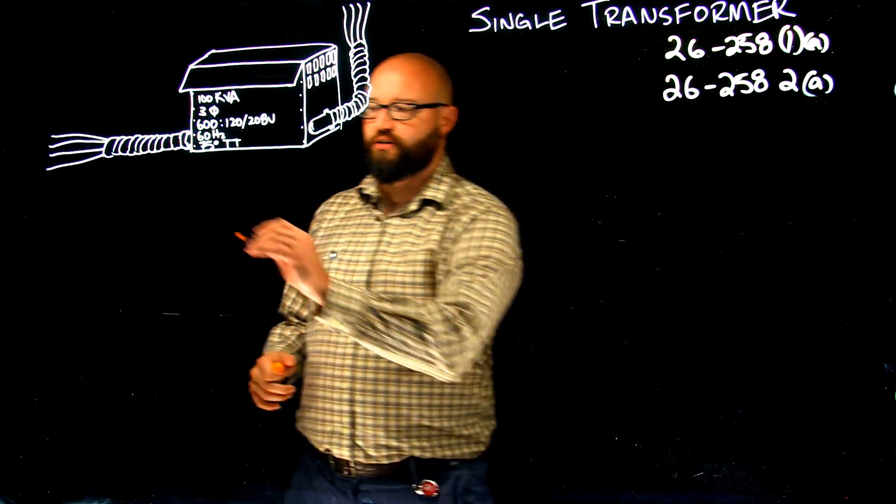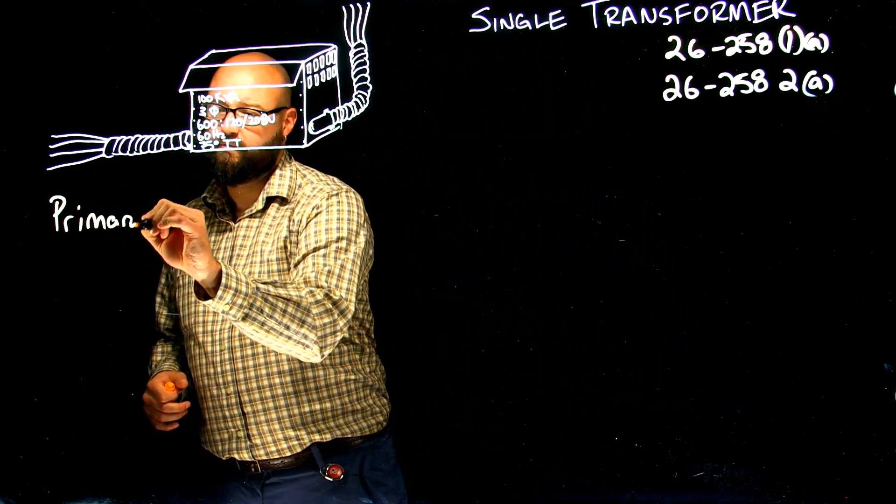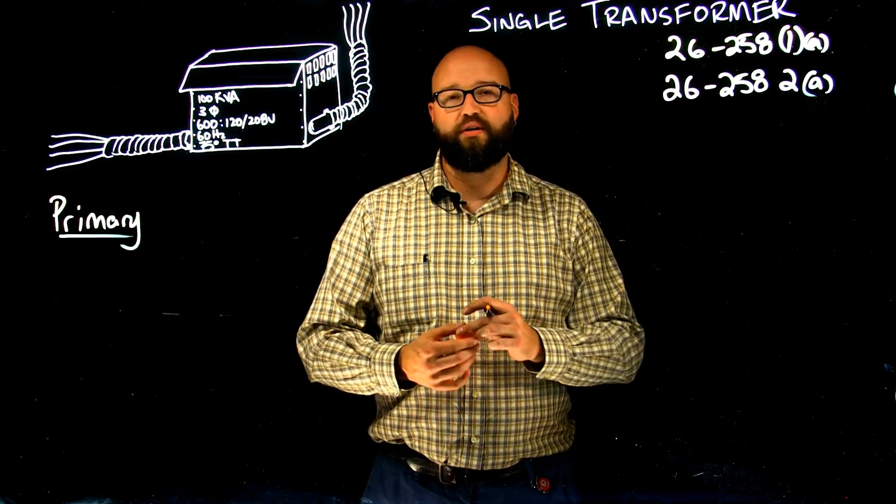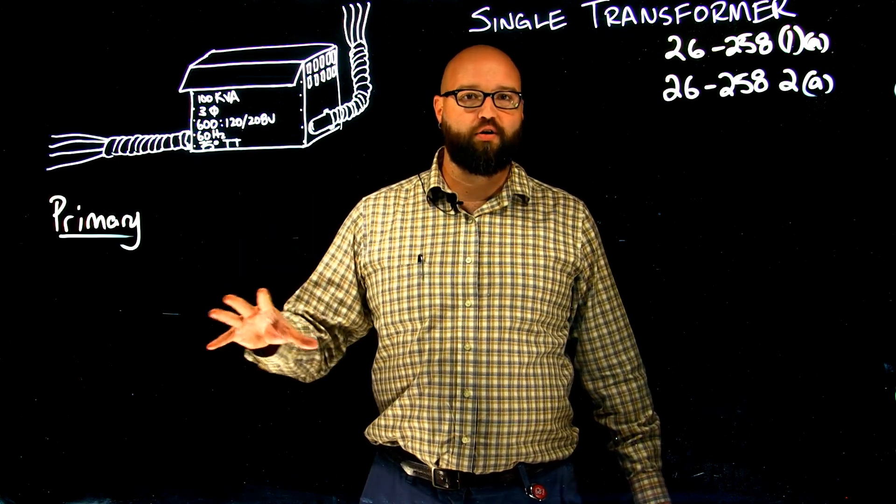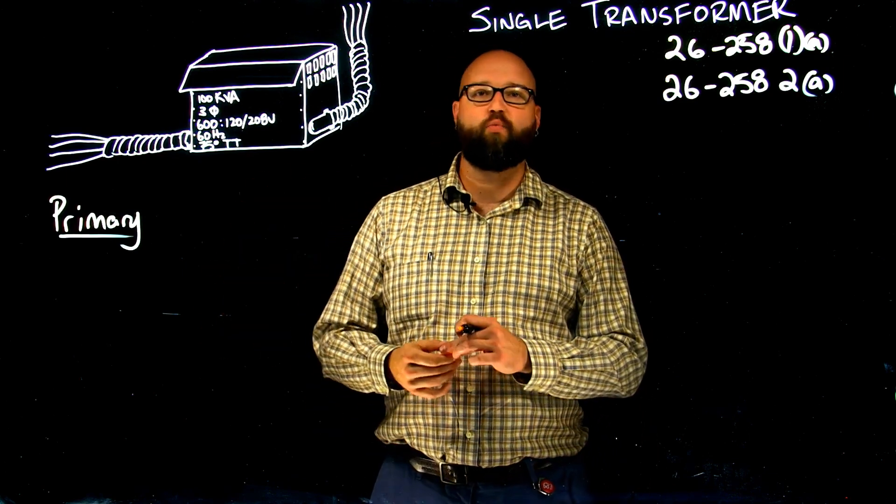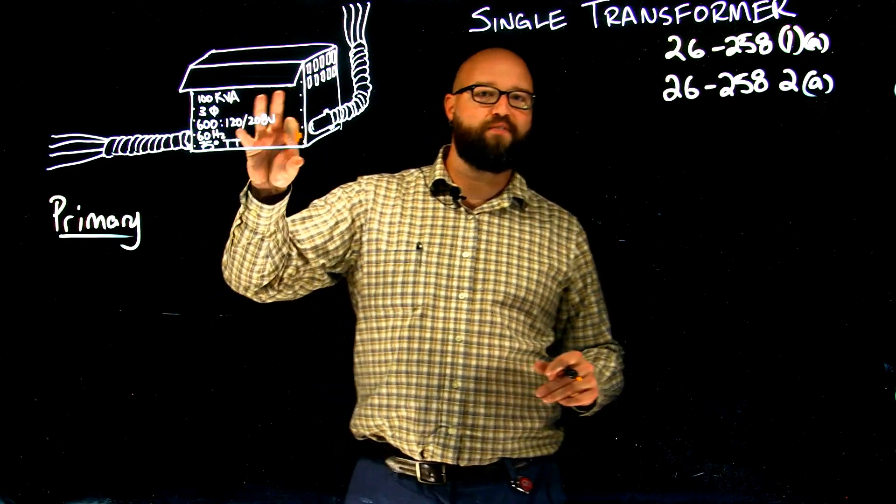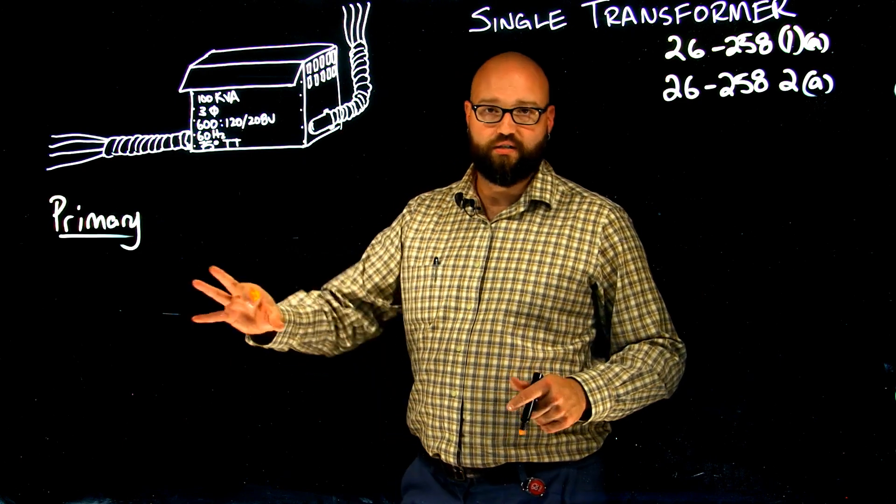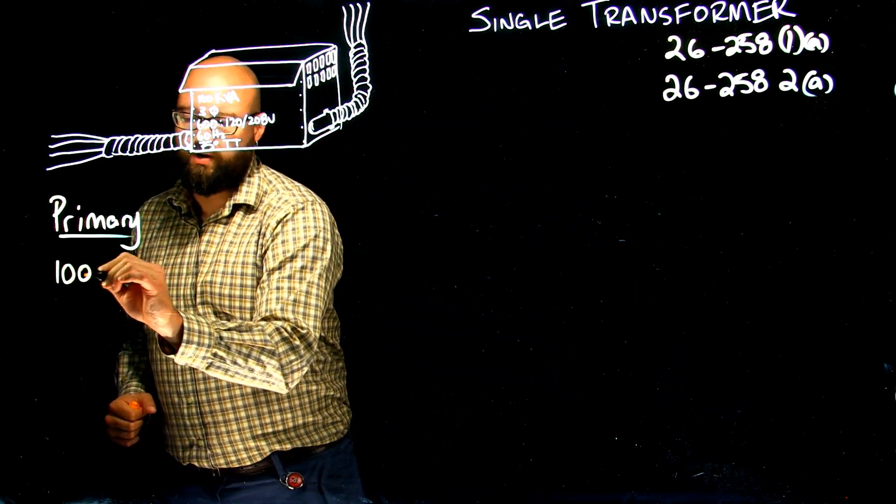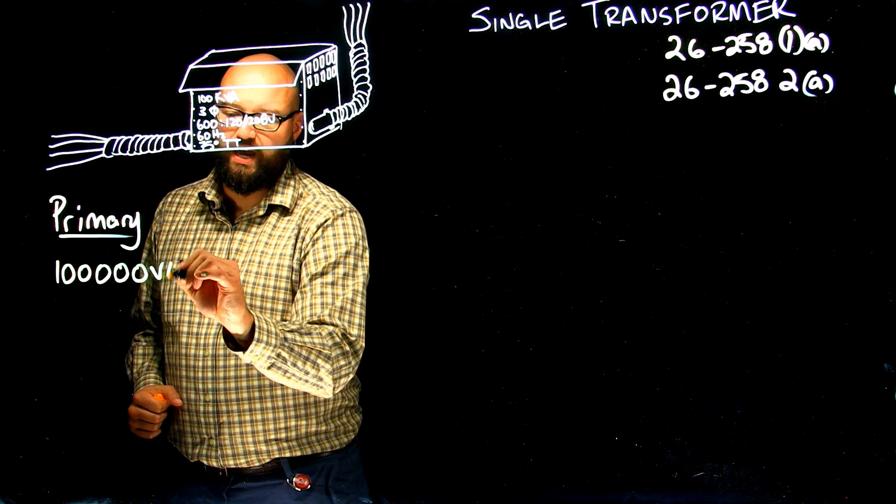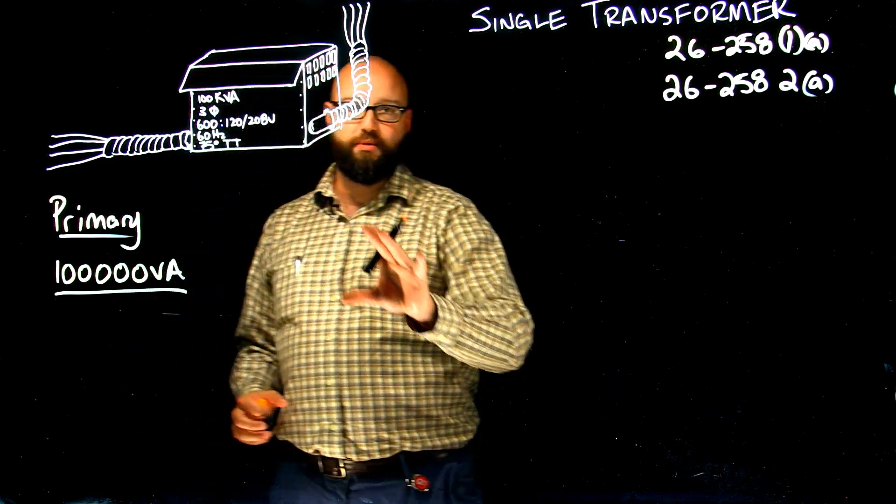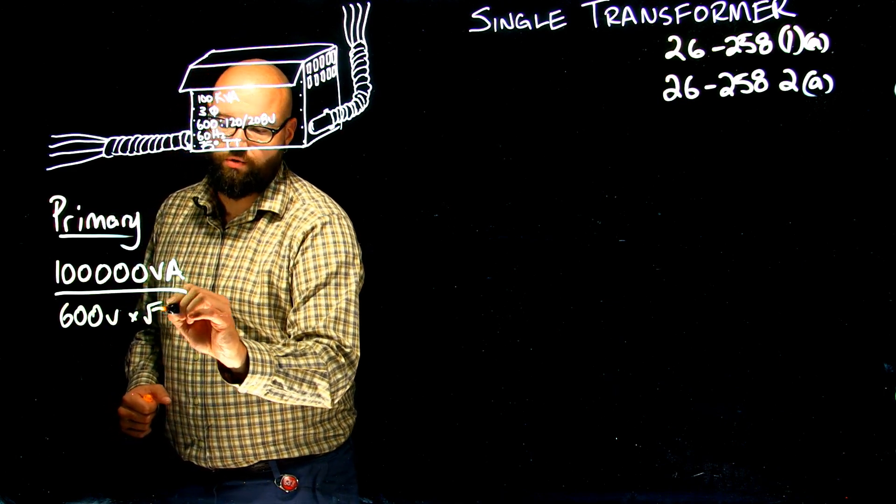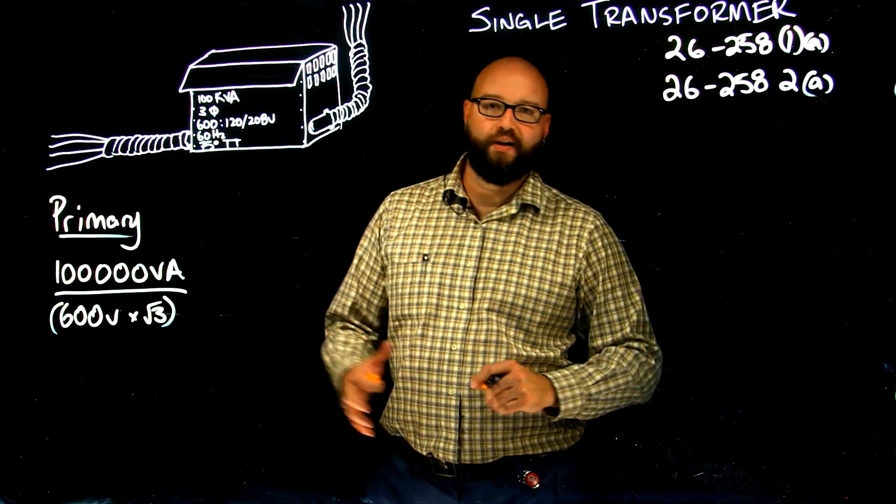Let's take a look at the primary side first. What the rule tells us is that we need to be no smaller than 125% of the rated primary current. So, first thing we need to find is what is that rated primary current. Because it's a three-phase transformer, we don't want to forget that crucial root 3 in our calculation. We have 100,000 VA divided by our primary voltage of 600 volts times root 3 because it is a three-phase transformer.